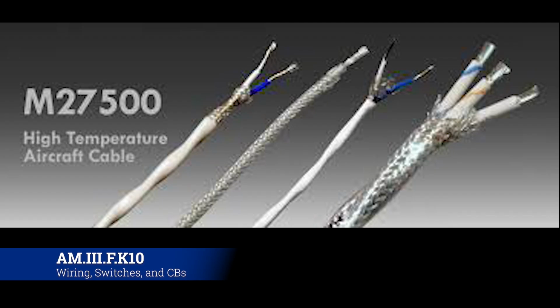Coax is generally a radio frequency cable—it goes to antennas and that sort of thing. You generally won't see that on the engine, but you may. Either way, coax has a single strand wire in the middle, then a dielectric that goes around it, and shielding on top of that. The single strand and that shielding can't touch, and if they do—which typically happens during terminations when installing new wires—that will cause a problem, so you don't want to do that.